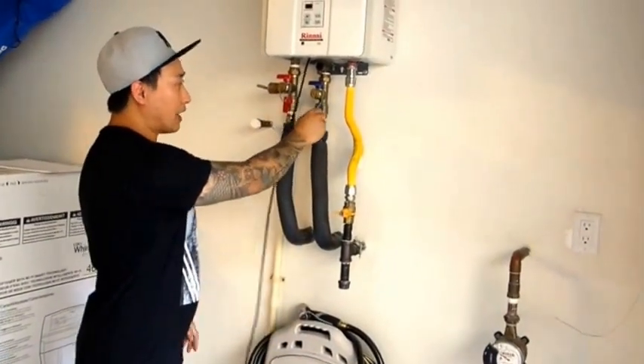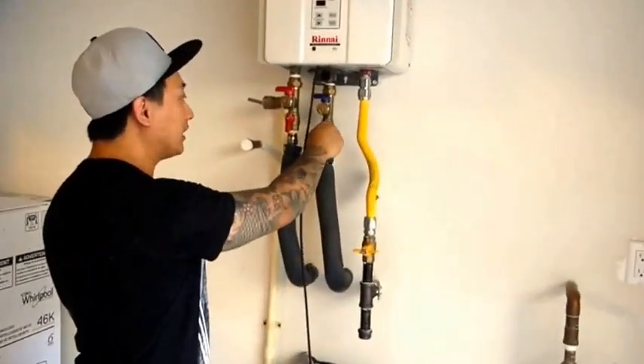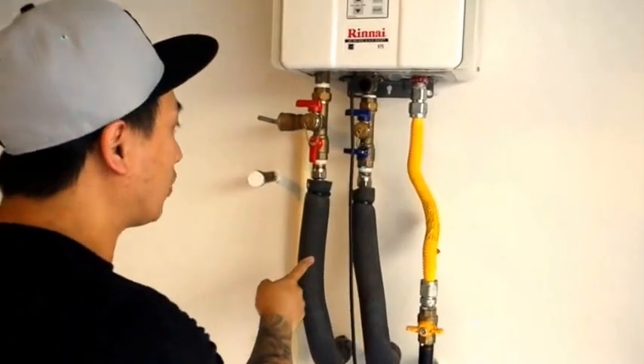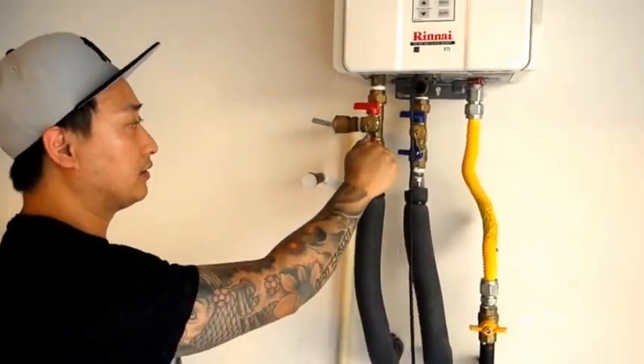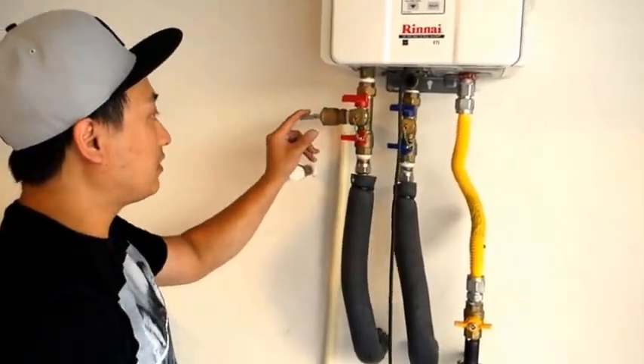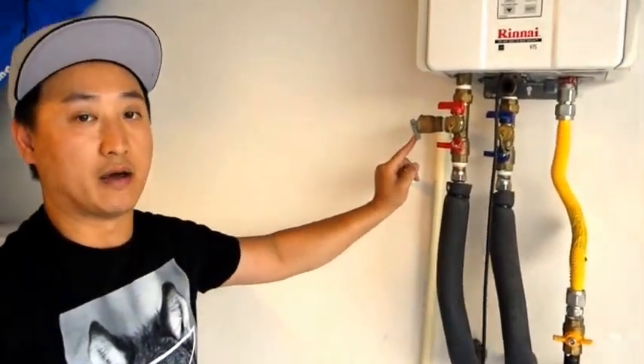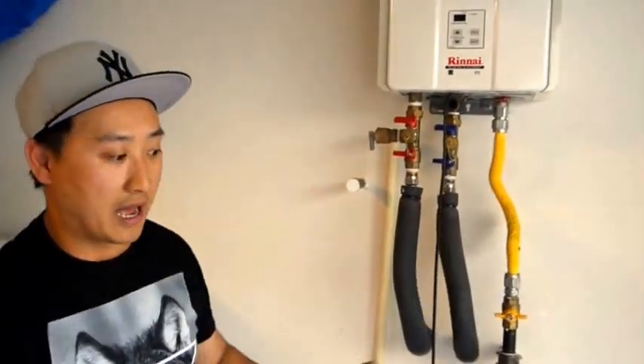I'm going to go ahead and close my cold water inlet, as well as close my hot water outlet. Then flip that down. You want to make sure you flip that back down afterwards, so you're not cycling the water outside rather than cycling it back in itself to flush it out.